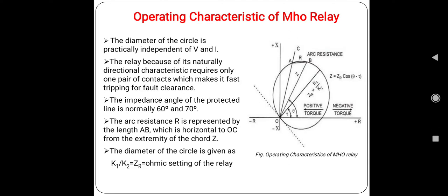It is a fact that the circle passes through the origin, which makes the relay inherently directional. The relay, because of its inherently directional characteristics, needs only one pair of contacts which makes it fast tripping for fault clearance and reduces the VA burden on the current transformers.